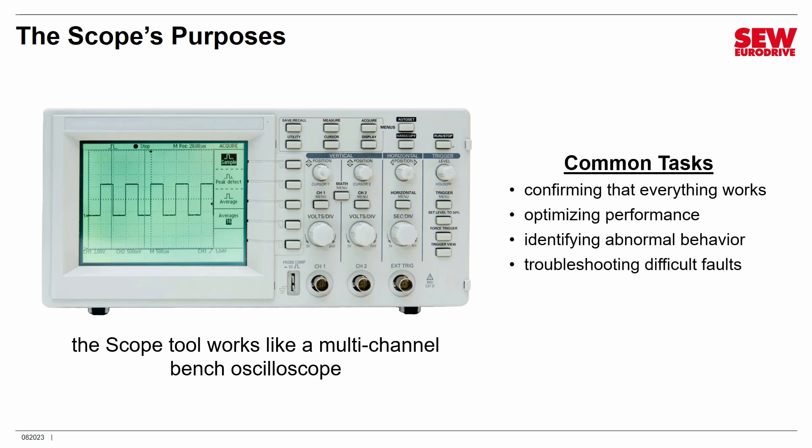The scope has four major purposes. First, it's often used just to confirm that your VFD is performing correctly — that it's ramping up and down in the right amounts of time. You can also use it for optimizing performance; the scope gives you a great visual way of doing that. You can use it for diagnostics and troubleshooting to get a clearer picture of abnormal VFD behavior. And finally, the scope is very good at dealing with troublesome faults — you can set it to watch different VFD parameters, and when a fault occurs, you can look at the trace to understand what caused it. We'll explore several of these and demonstrate how to set them up.